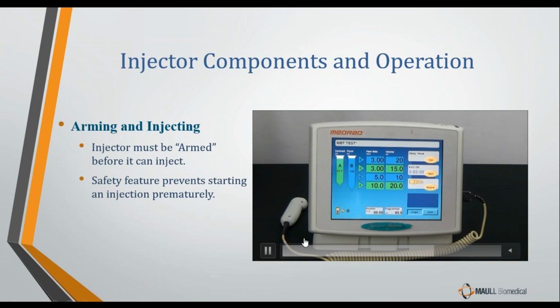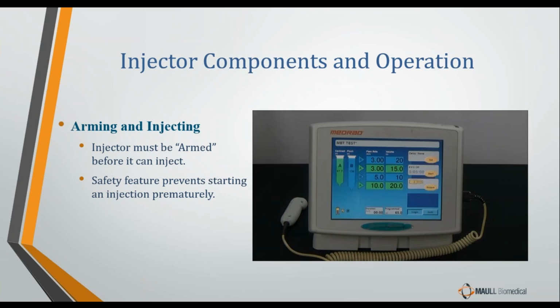We are flashing armed. Now, the injector does not actually check for air in the syringe. The syringe could have nothing but air in it. But if the operator says, yep, I've checked for air and we are cleared, the injector is now armed and it will shoot. So this is a safety feature that prevents us from injecting air into the patient, and it also prevents us from inadvertently injecting the patient before we were ready to, because it needs to be a two-step process. You can't just pick the button up and hit it by accident and start the injection prematurely. We want to make sure that we are truly ready to start injecting by arming the injector first.